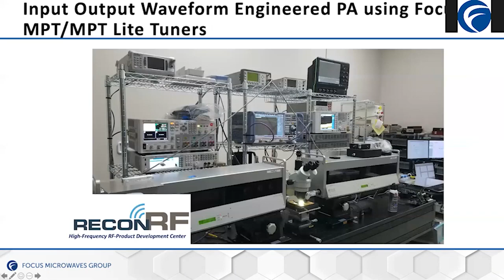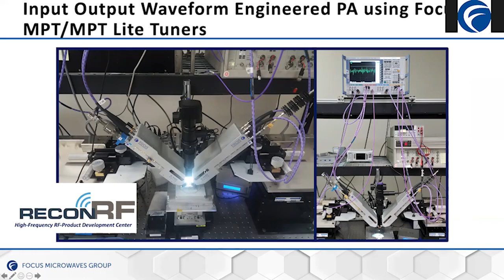Again, if we look at a live setup, which we showed yesterday, this is a 0.8 to 18 gigahertz system that controls not only the fundamentals, but the harmonics as well. Same here with this example of a 10 to 67. So if you want to do 5G design where you're tuning at 28 gigahertz and controlling the harmonic up to 56 gigahertz, in some cases higher, you could do it with these kinds of setups where you have harmonic tuning on both the input and the output with passive tuners.